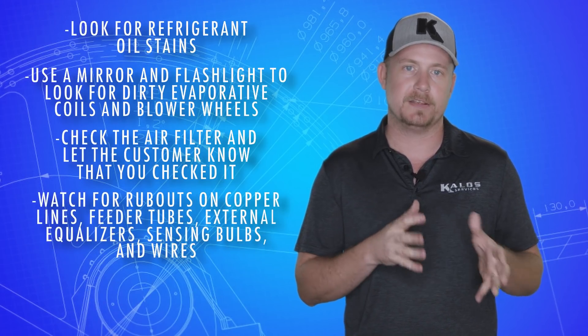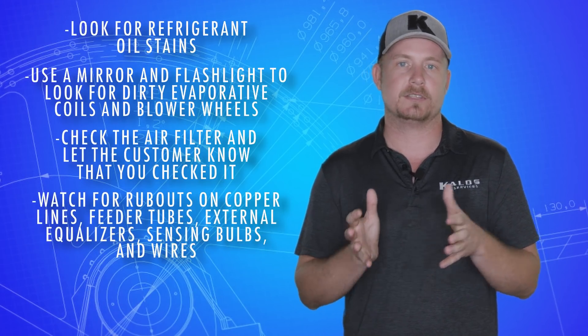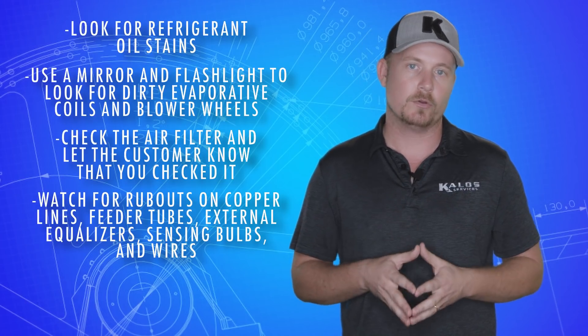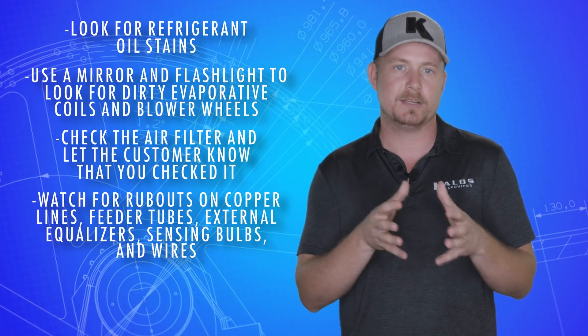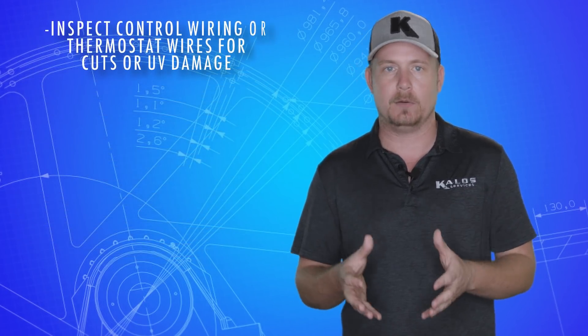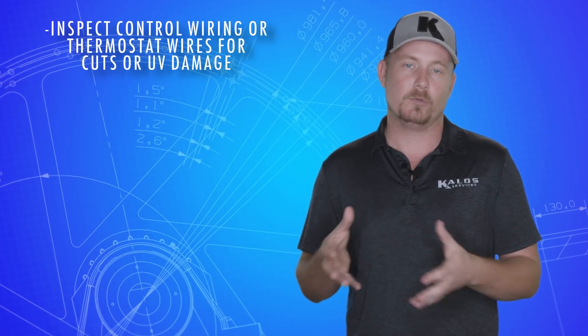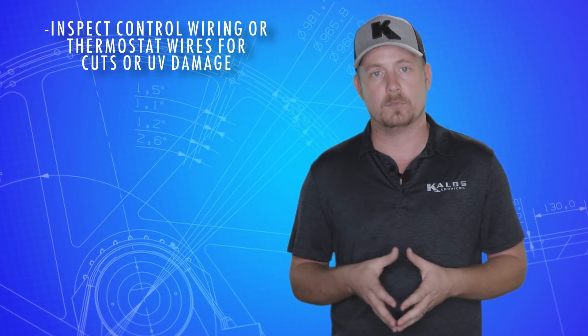Watch for rub outs on copper lines, feeder tubes, external equalizers, sensing bulbs, and wires. You can often find or prevent a problem just by looking for areas of contact between tubes and or wires. Inspect control wiring or thermostat wires for cuts or UV damage outside. If the weed whacker doesn't get the wire, often the sun will.